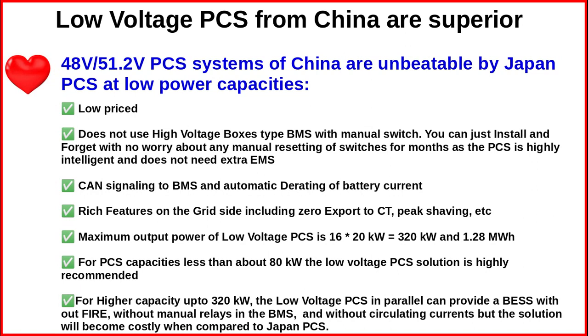Regarding the maximum output power of these low voltage PCS, 16 of them can be paralleled with 20 kilowatt maximum each. This comes to a PCS maximum capacity of 320 kilowatt and an energy capacity of say 4 times, which is 1.28 megawatt hour. For PCS capacities less than about 80 kilowatt, the low voltage PCS solution is highly recommended. The last point is very, very important. For higher capacity up to 320 kilowatt, the low voltage PCSs in parallel can provide a BESS without fire.